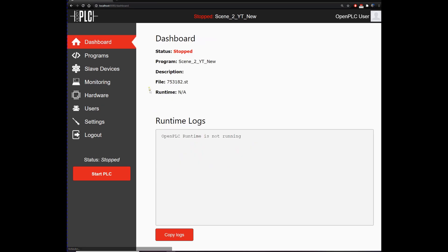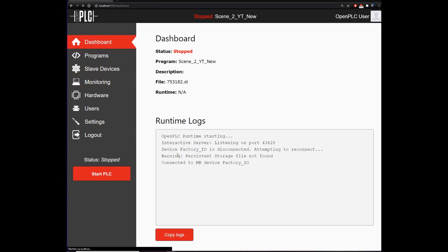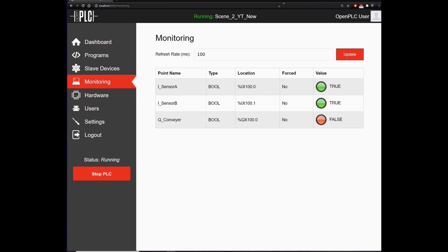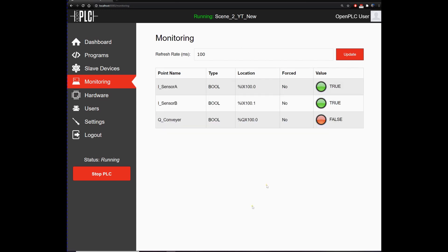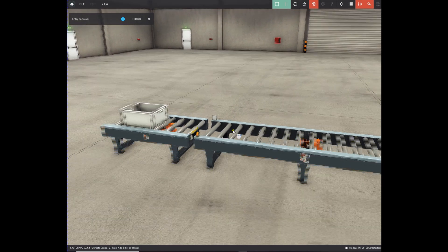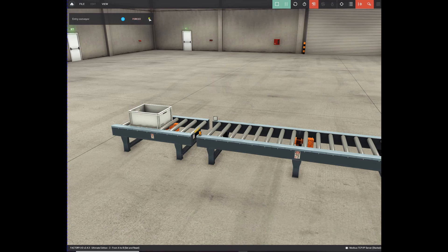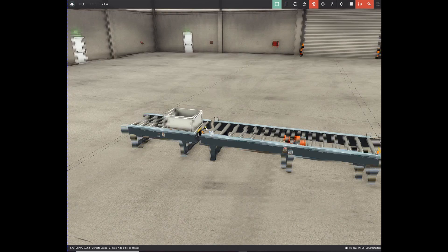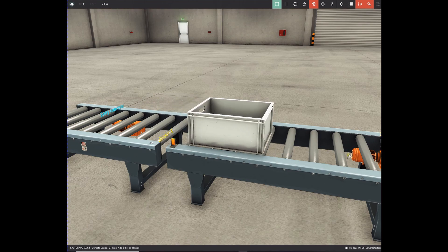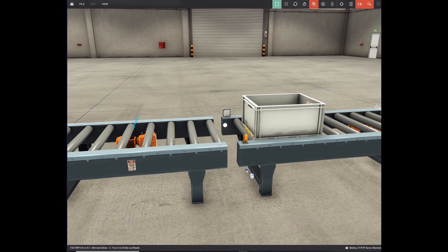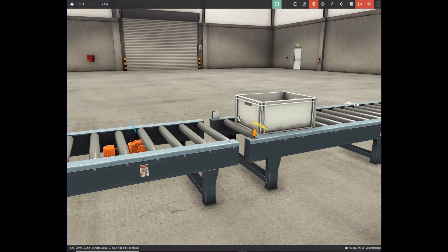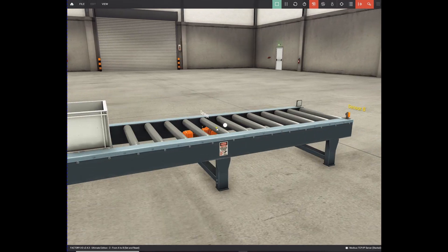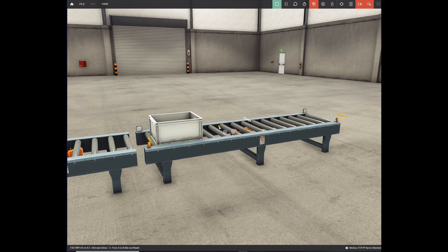Now it's running. You can monitor inputs and outputs - Sensor A is true as an input because it sees a reflector, Sensor B also, and the conveyor is off. We open Factory IO, start the scene, and the conveyor will run. But as you can see the conveyor will stop, because it only runs when Sensor A sees the box. It doesn't see the box right now so it stops. How do we solve this?